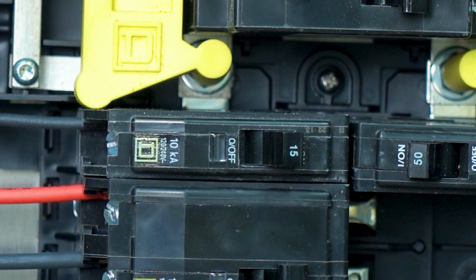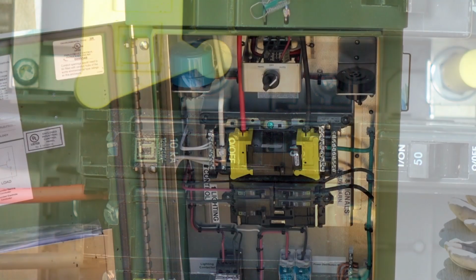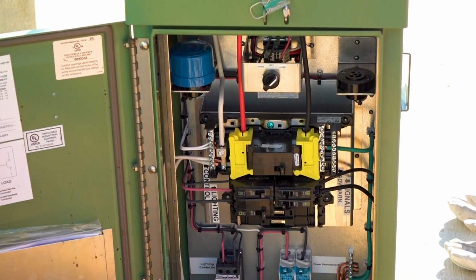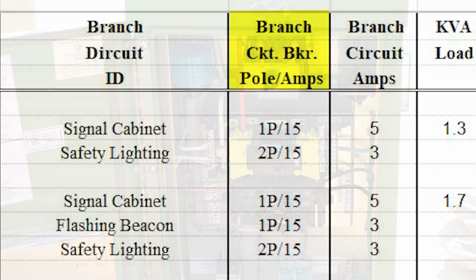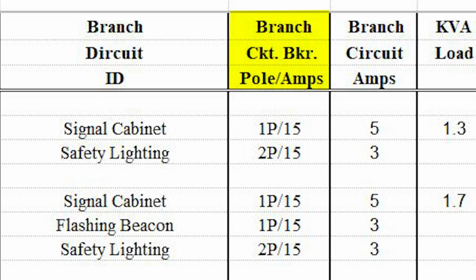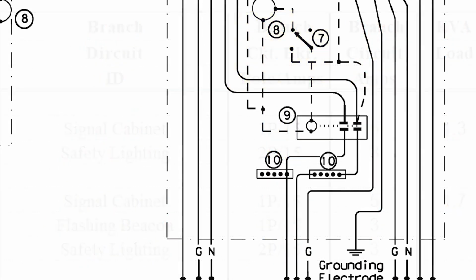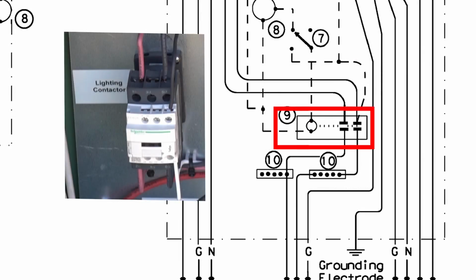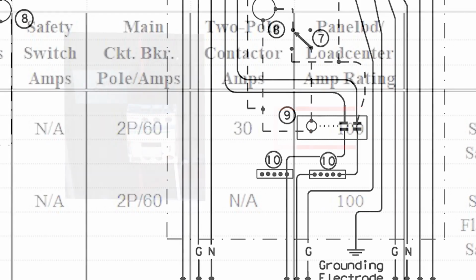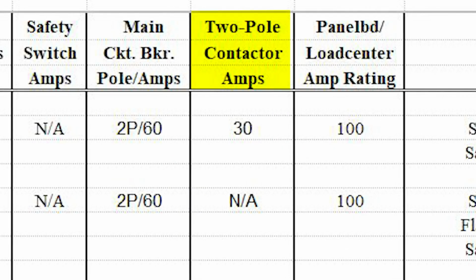The inspector should confirm that a single-pole 15-amp breaker provides power for the lighting control circuit. The ampere rating and number of poles for each branch circuit breaker should be confirmed by reference to the electrical service data chart. Next, the inspector should inspect the lighting contactor. The lighting contactor is a magnetically operated switch that opens and closes the circuit to the light fixtures. The ampere rating and number of poles can be found on the electrical service data sheet.